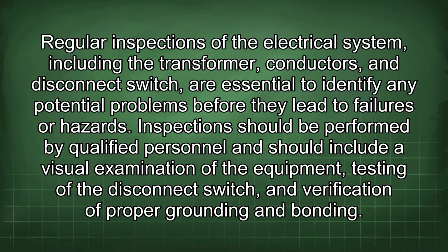Regular inspections of the electrical system, including the transformer, conductors, and disconnect switch, are essential to identify any potential problems before they lead to failures or hazards. Inspection should be performed by qualified personnel and should include a visual examination of the equipment, testing of the disconnect switch, and verification of proper grounding and bonding.